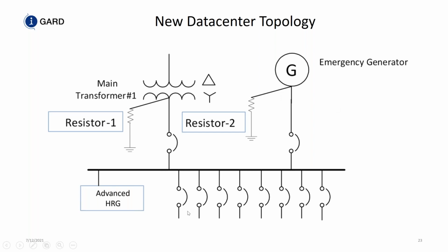So we're looking at the loads to determine where the fault is. Because we monitor the voltage on the bus, we can determine if there's a ground fault on the system by the elevation of the neutral and the de-escalation of one of the phases with respect to ground in terms of potential.